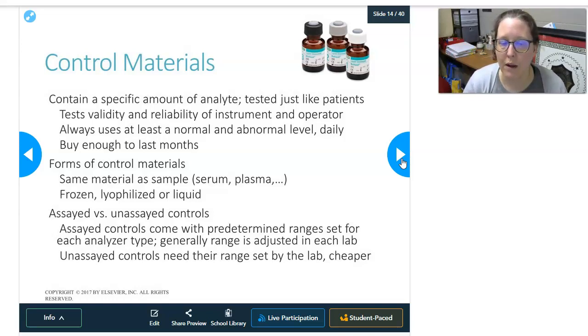So with an unassayed control, you don't have a target, and so you would have to set the range. The way you would set the range is when you do that whole month of parallel testing, you're using all those data points on the new lot, for every test and every level of QC, to determine what the range is going to be for this new lot number of QC. And I'll say it again, unassayed are cheaper.